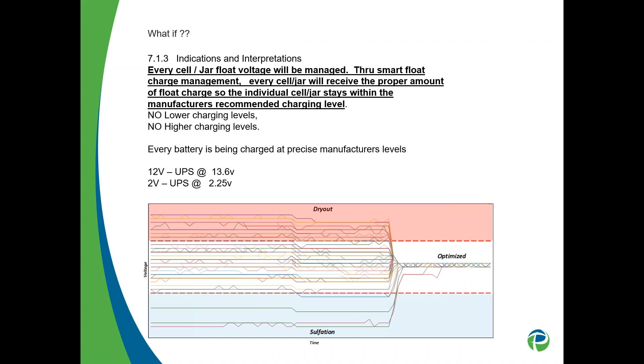So if we keep those batteries away from those dry-out zones and sulfation zones, you're going to optimize your battery system, optimize your capital expenses, and increase the reliability of your battery systems, because you're keeping the batteries at pristine value, and this is going to increase the reliability of your critical operation.